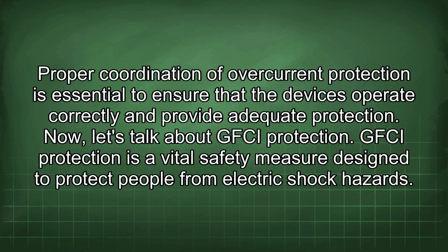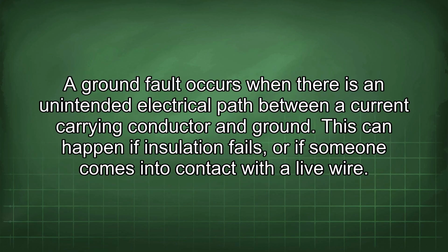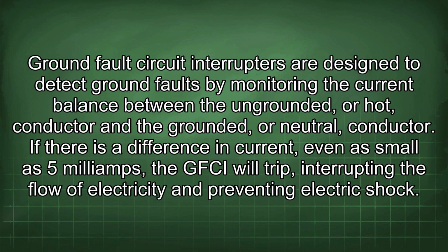Now let's talk about GFCI protection. GFCI protection is a vital safety measure designed to protect people from electric shock hazards. A ground fault occurs when there is an unintended electrical path between a current-carrying conductor and ground. This can happen if insulation fails or if someone comes into contact with a live wire. Ground fault circuit interrupters are designed to detect ground faults by monitoring the current balance between the ungrounded, or hot, conductor and the grounded, or neutral, conductor. If there is a difference in current, even as small as 5 mA, the GFCI will trip, interrupting the flow of electricity and preventing electric shock.